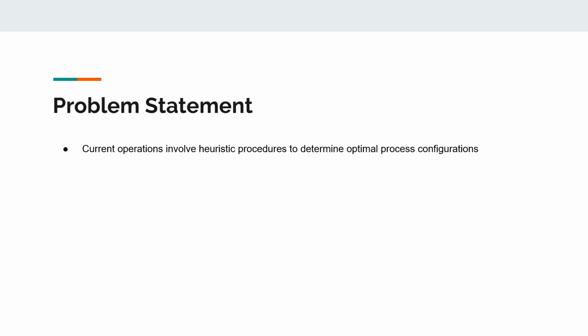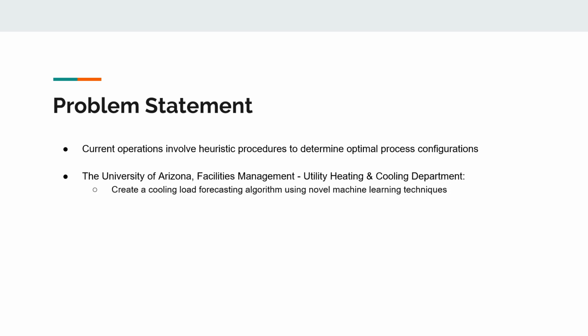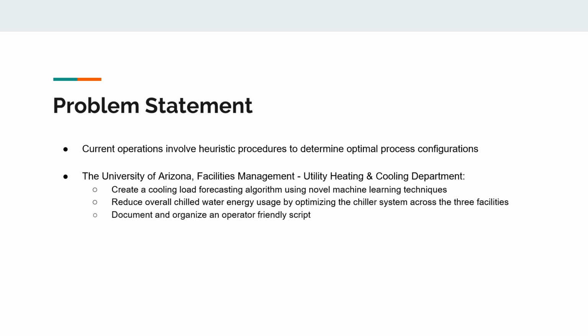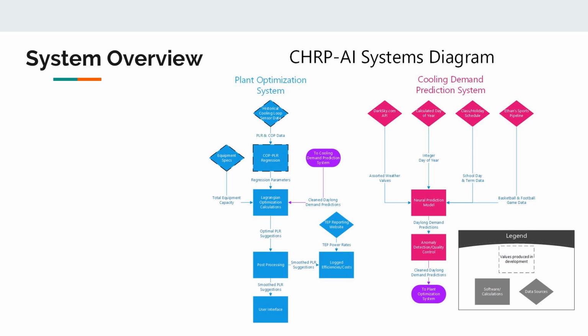The Utility Heating and Cooling Department has asked us to find a mathematical and quantitative approach to these procedures by creating a cooling load forecasting algorithm using novel machine learning techniques, reduce overall chilled water energy usage by optimizing the chiller system across the three facilities, and document all programming procedures and organize scripts such that it is easily accessible to operators. The CHRP-AI system is organized into unique modules that function independently of downstream elements. Each module is implemented as a class in Python, where pertinent metadata and operational methods can be called.